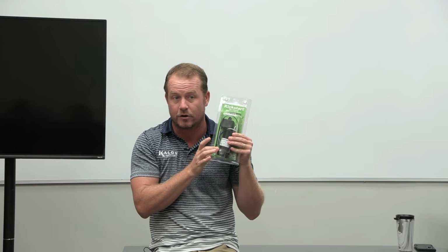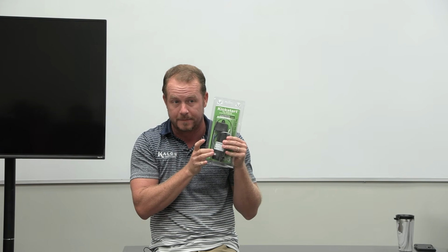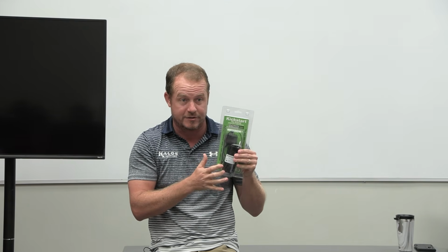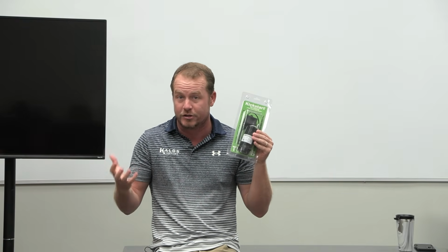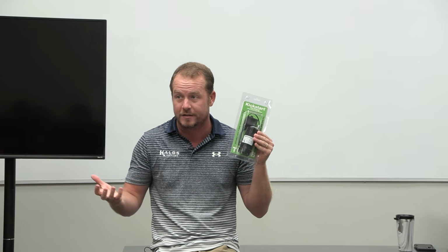This is a very touchy business. Fine differences can make a big difference in how long this start capacitor stays in place. This start capacitor is only adding current to the start winding. It has nothing to do with the run winding, so it's supposed to come out of the circuit. That's why we have this relay. We don't want this big boy staying in there at 150 microfarads or 200 microfarads or whatever it is, right? That's too much current for that start winding to run all the time. So this relay's got to take it out.